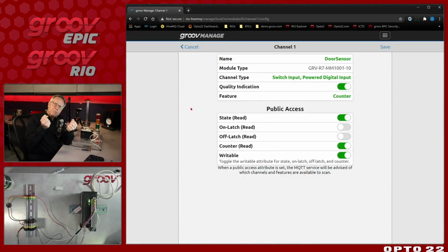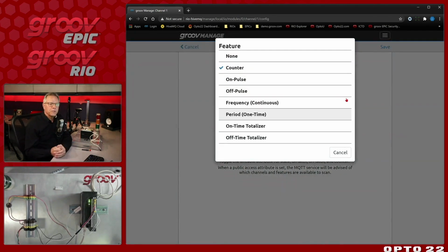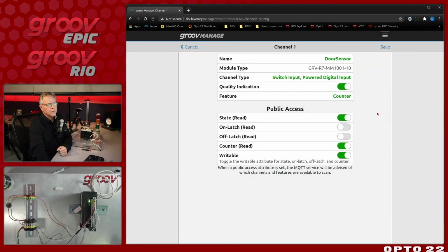Now on some of those inputs, where in this case we're getting a door sensor, it could be a proximity sensor to count how many products a machine makes, or a sensor to tell if a machine is on or off for OEE applications. So we have features that allow us to configure that input to be even smarter. In this case it's a counter, but it could track how long the door was open or closed, or how many times it happened, which is what I'm doing here.